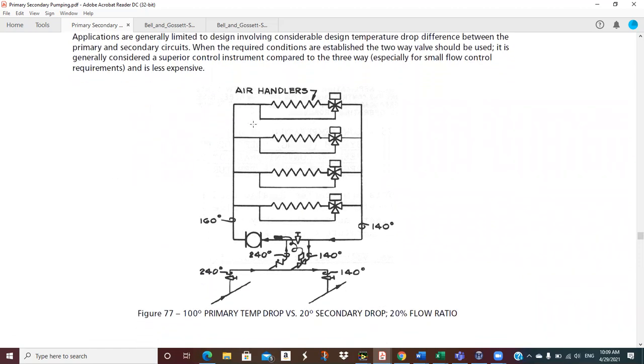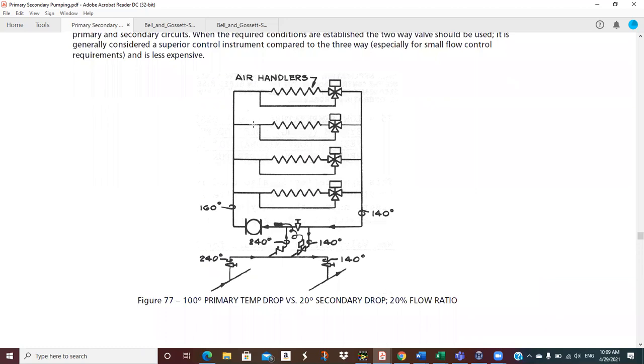So all of these are going to be shown for situations where we can put really hot water into it. So he's saying here that my primary drop, say I'm coming up at 240, I'm going back at 140. So I've got a 100-degree drop in the primary, and I've got a 20-degree drop up here. So for your flow ratio, you can just take that. So that says that's 20%. So my flow ratio is going to be 20%. So that's going to lend itself to it. You've got to make sure your restrictive pressure drop is correct as well.